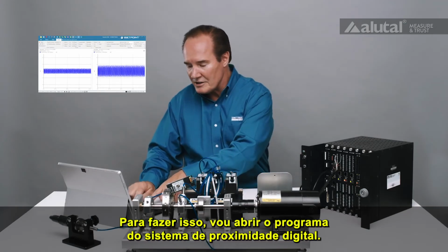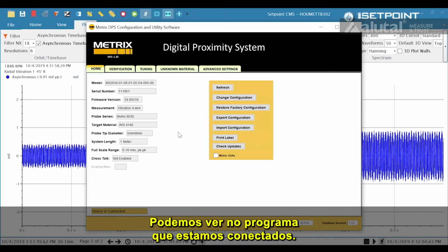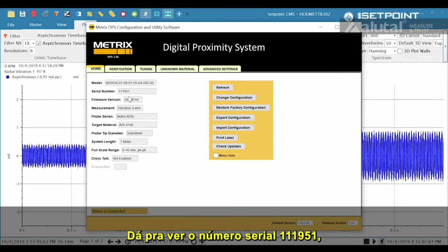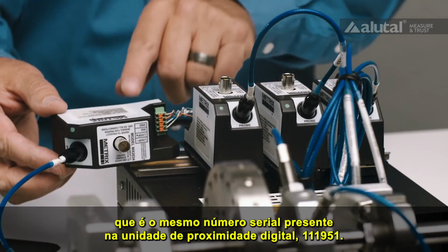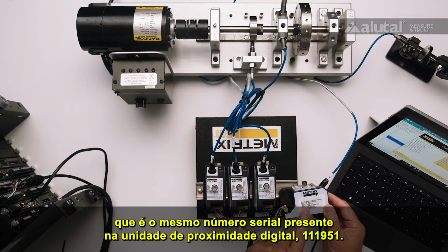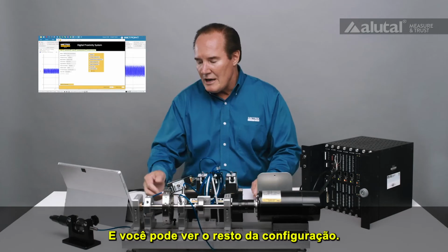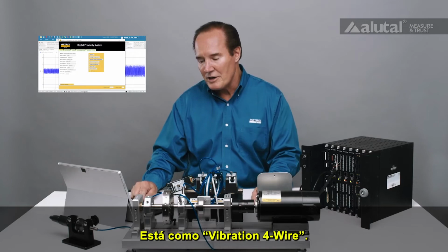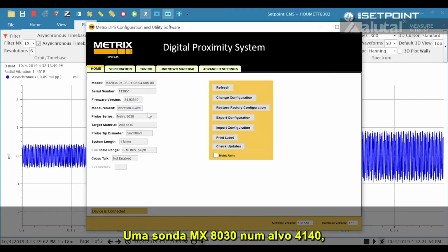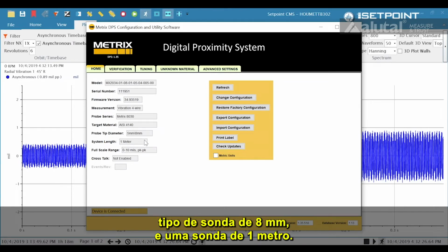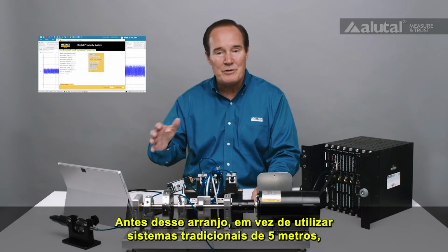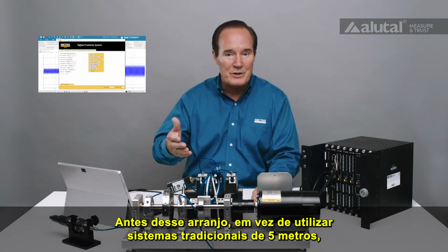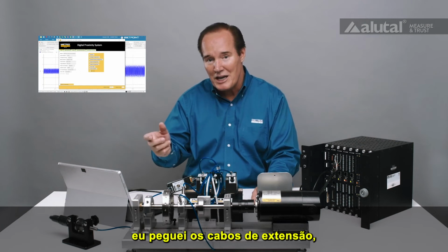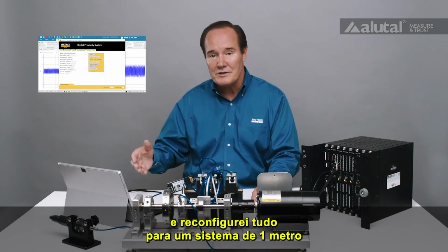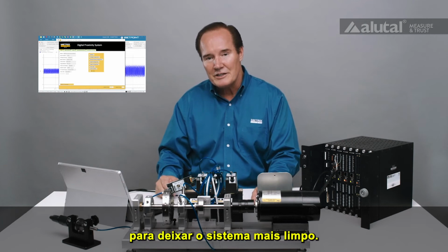And to do that, I start the digital proximity system software. We can see on the software that we're already connected. You can see the serial number 111951, and that's the same serial number that's on this digital proximity unit, 111951. And you can see the rest of the configuration. This is vibration 4-wire. We're looking with MX8030 probes at a 4140 target, 8mm probe type, a 1-meter probe. And that's one thing I did before this setup. Instead of having the traditional 5-meter systems, I just took out the extension cables and reconfigured everything for a 1-meter system to make the system look a little bit cleaner. Makes it easier for us.